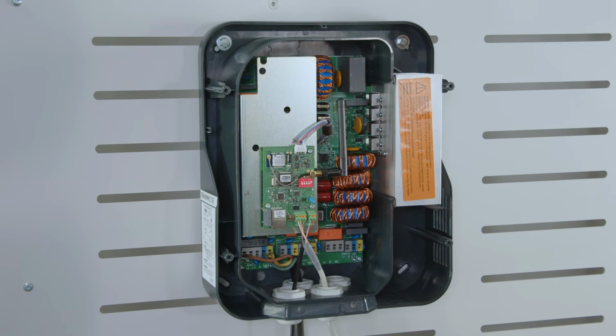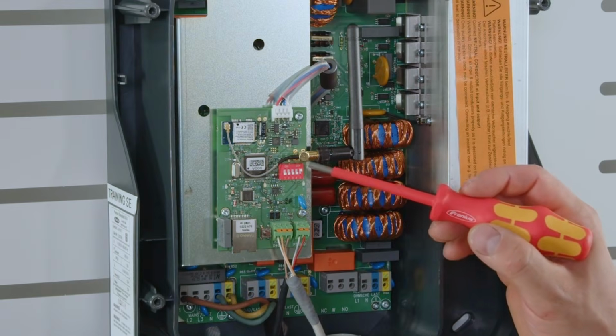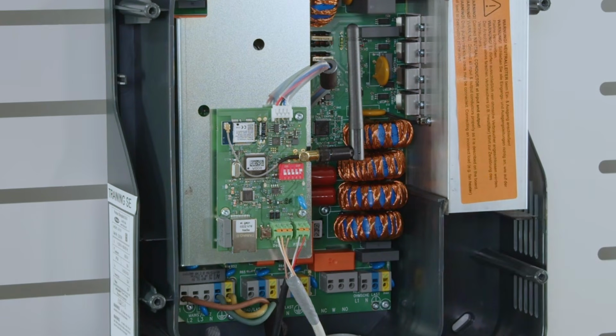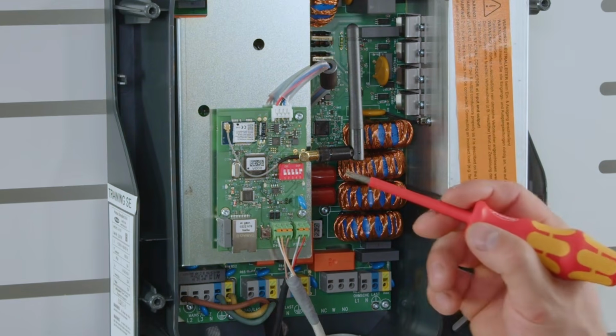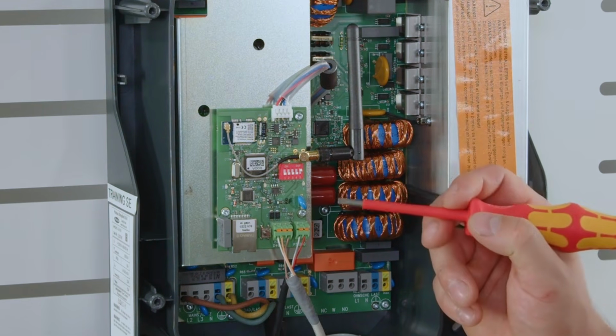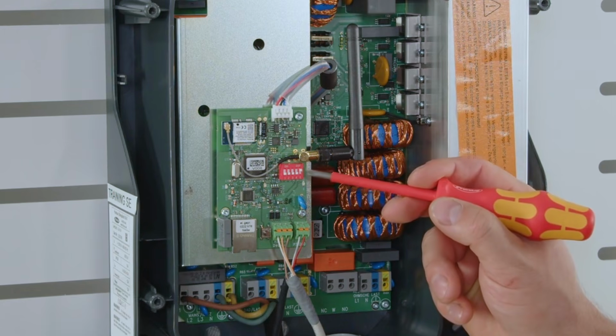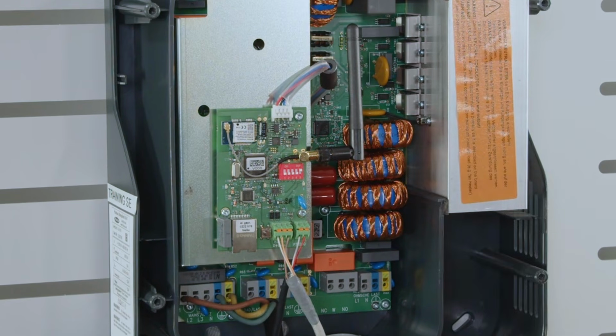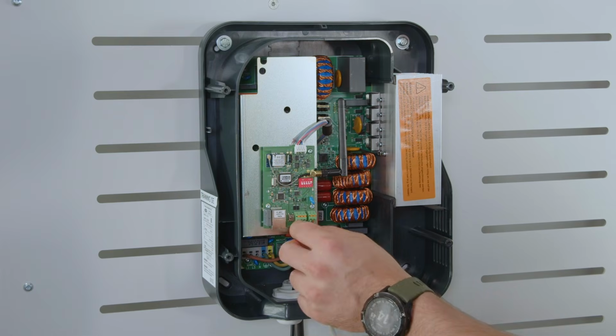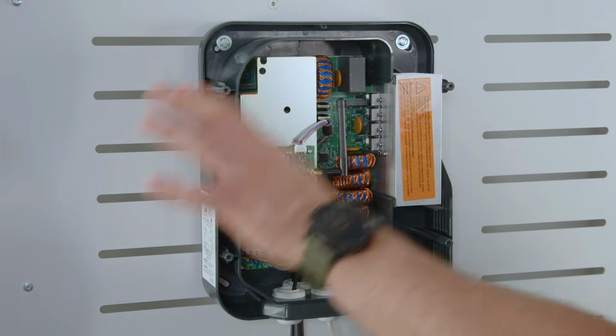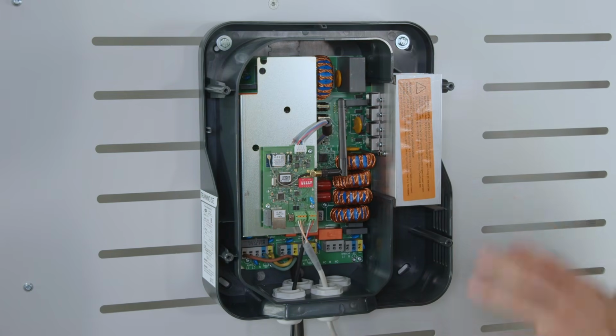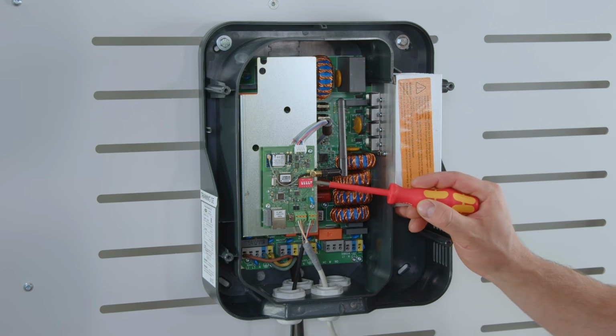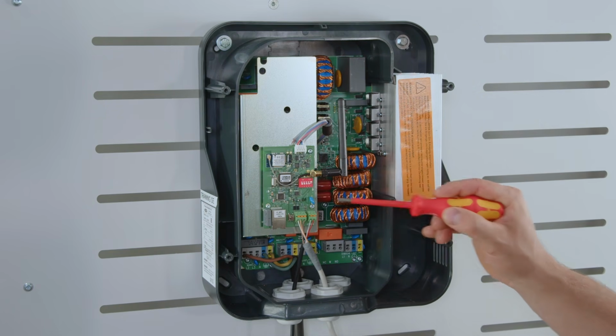Now, if we use RS485, don't forget there is this set of buttons or dip switches at the top here. Can be red or some versions also blue. And you can forget about all of them, but number 5. The dip switch number 5 would symbolize our 120 ohm resistance. So in our case, this is our end component. We go directly from here with the Modbus cable to the inverter.